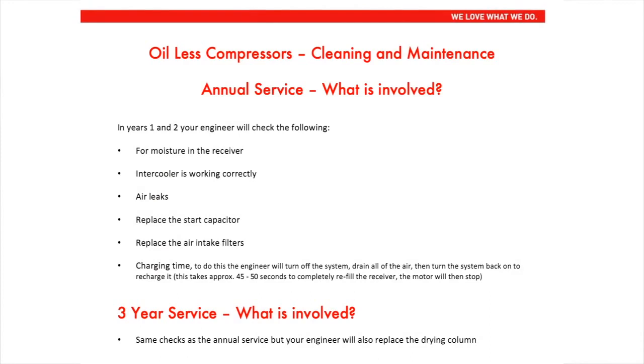Annual service, what is involved? In years 1 and 2, your engineer will check the following: for moisture in the receiver, that the intercooler is working correctly, and for air leaks. They'll replace the start capacitor and replace the air intake filters.